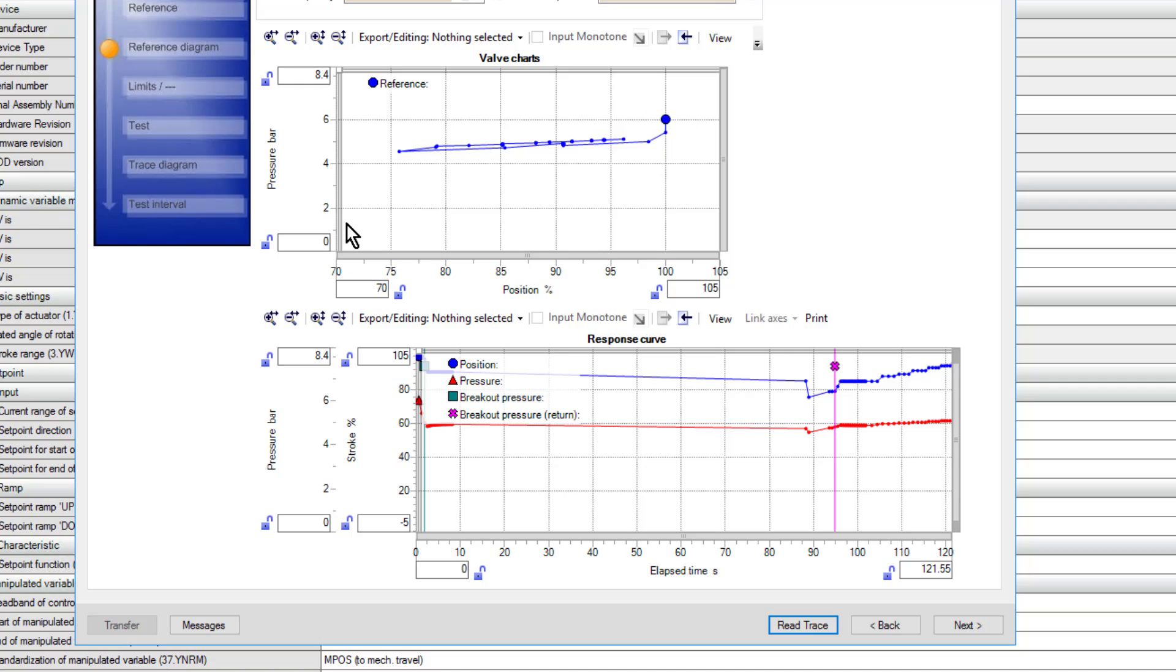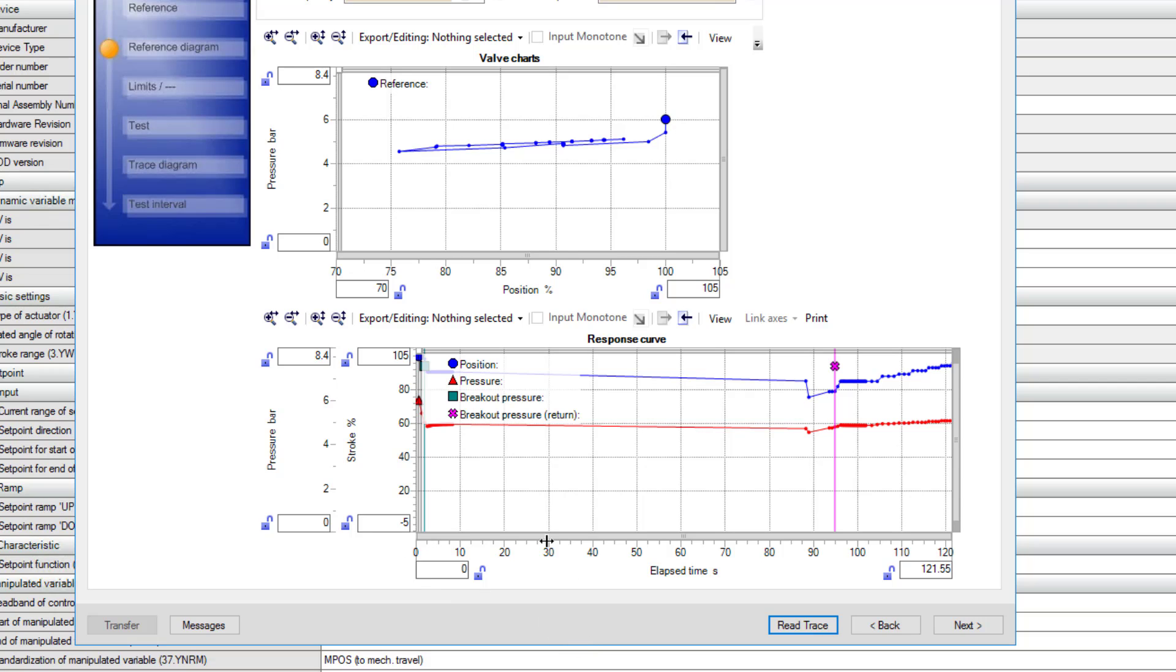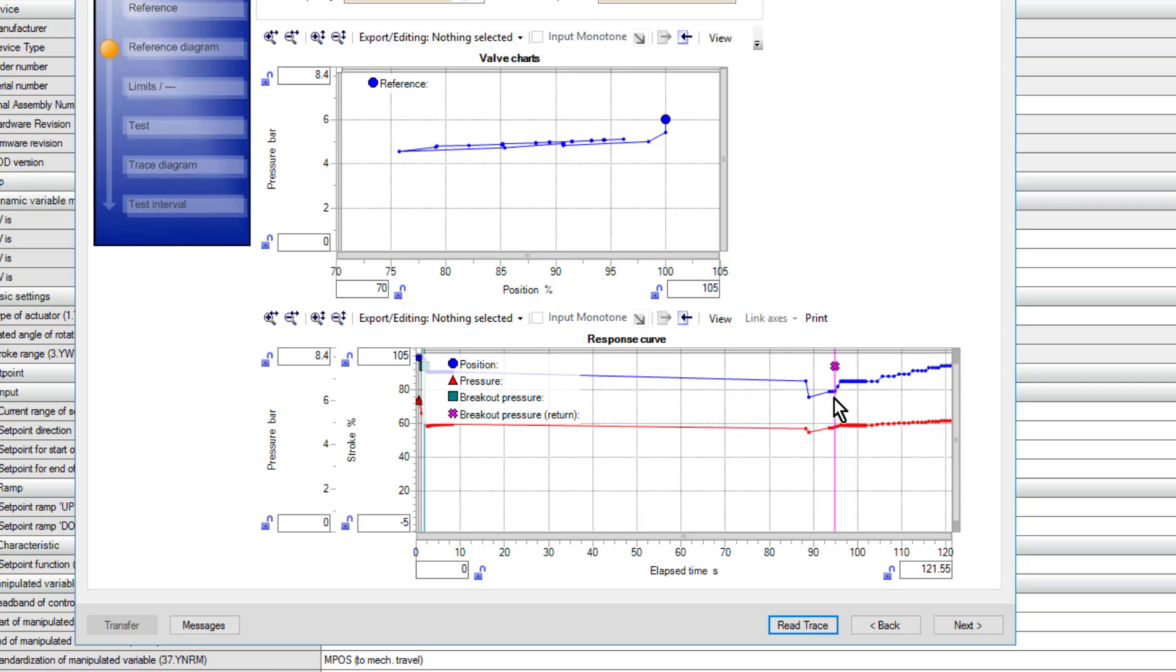You will see that we have our pressure and our position, so we can see the actual trend or the signature of the partial stroke test. Then down here we have the position and the pressure over time - slightly different trend, but this is probably the one that's easier to understand because you can see here the step down and then it comes back up. If we click next.